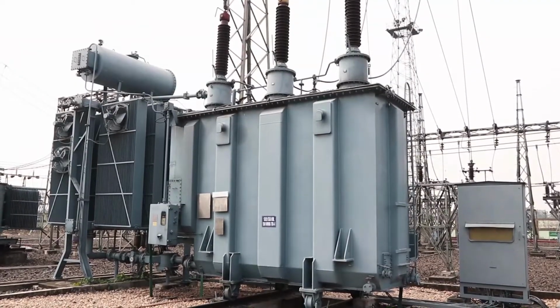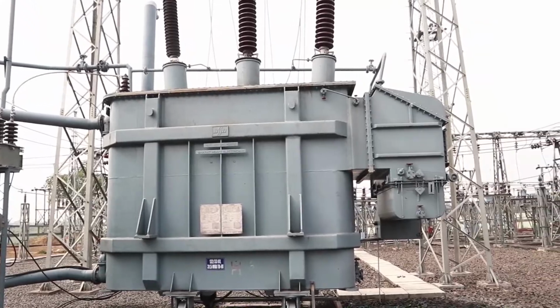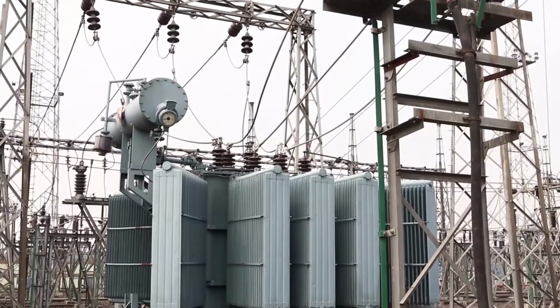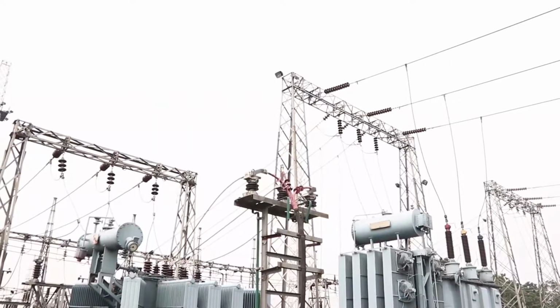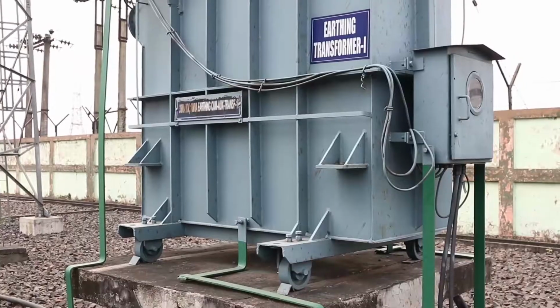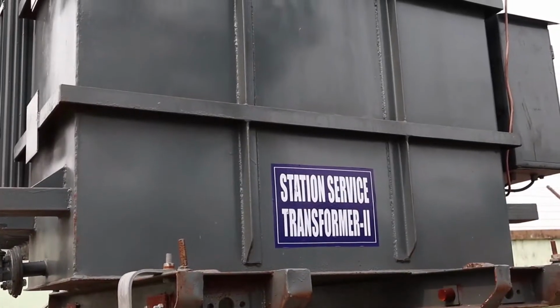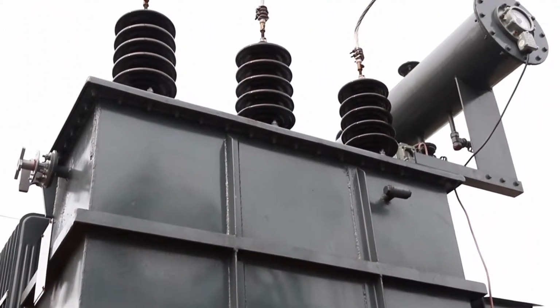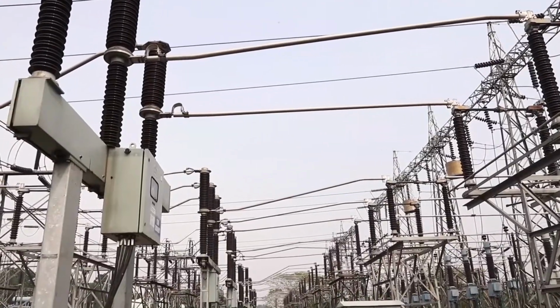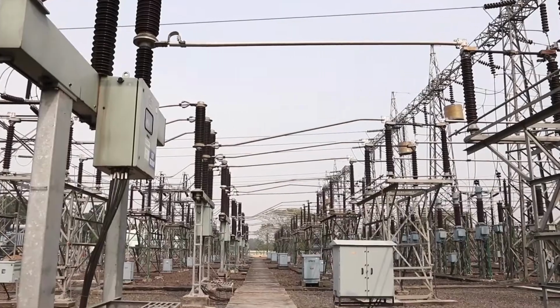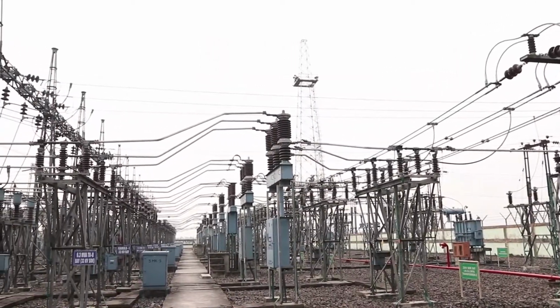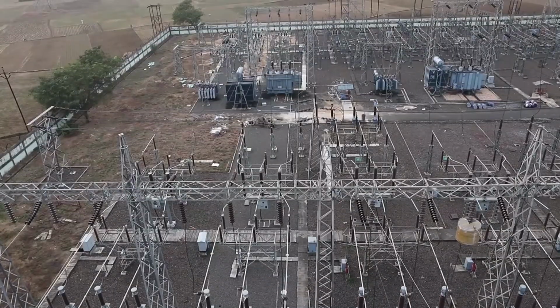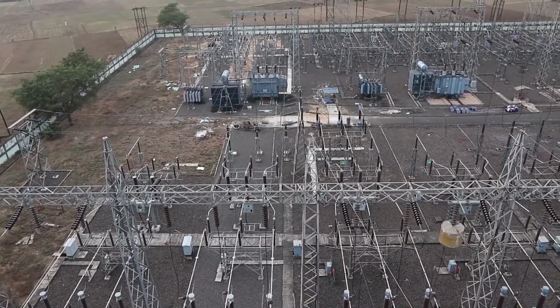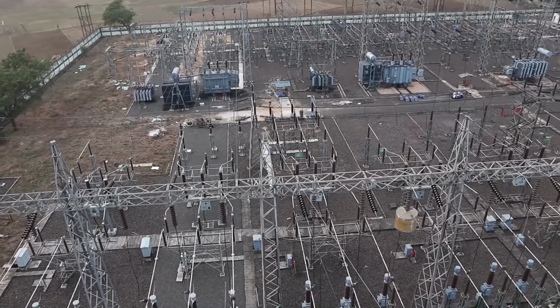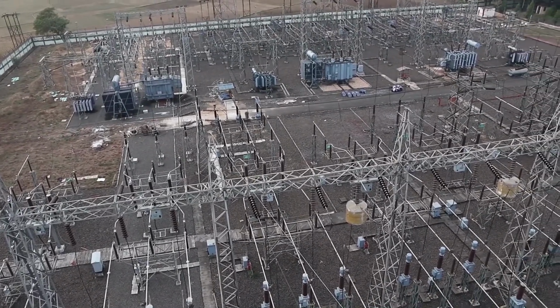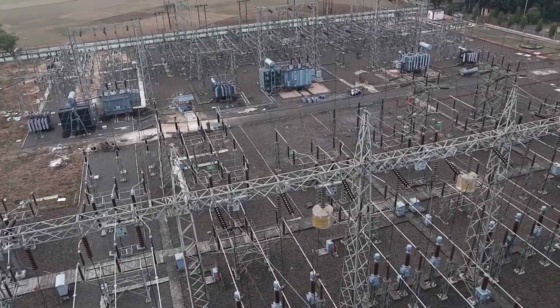At present, there are 3 numbers of 132 by 33 kV and 3 numbers of 33 by 11 kV power transformers, 2 numbers of station cum earthing transformers, and 2 numbers of 33 by 0.4 kV station service transformers. Presently, 9 numbers of 132 kV bays and 14 numbers of 33 kV bays are there. It has the total installed capacity of 1 into 50 plus 2 into 31.5 MVA plus 3 into 6.3 MVA.